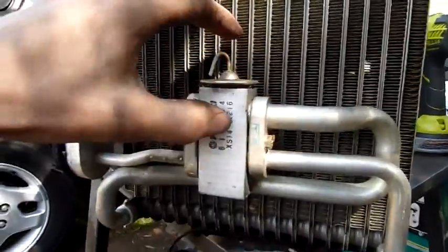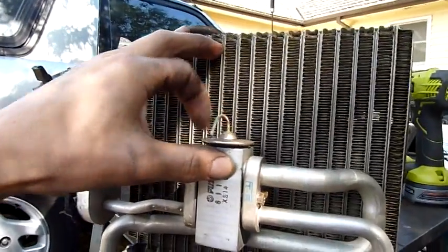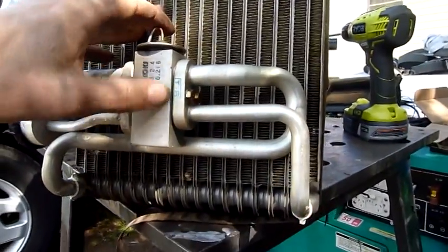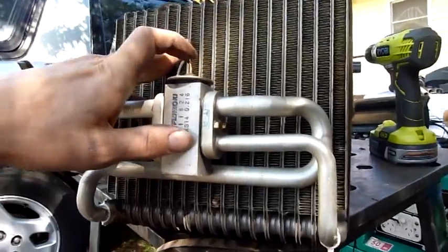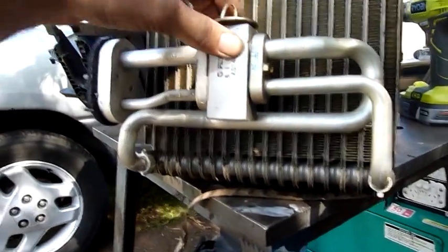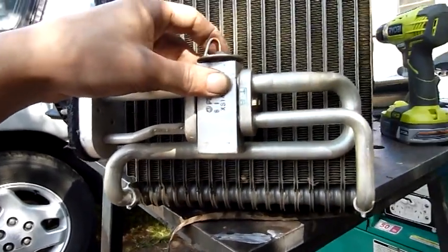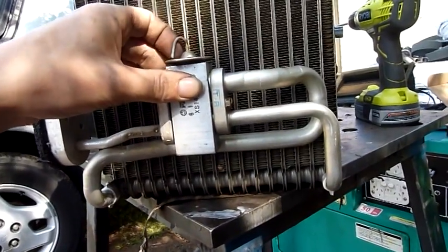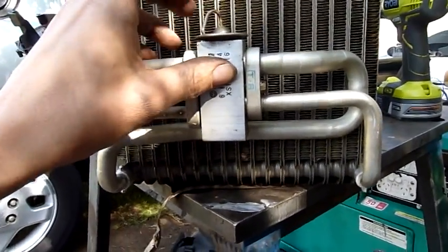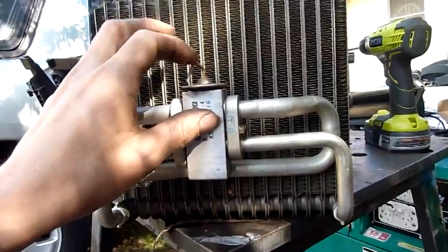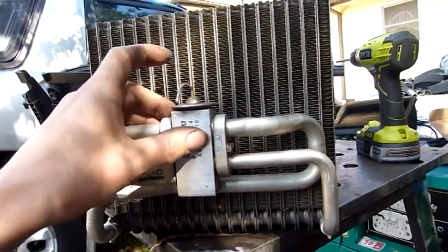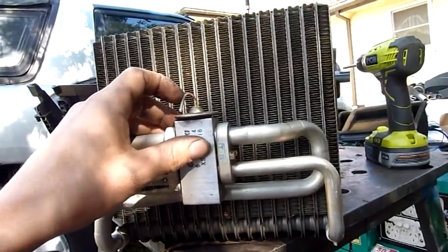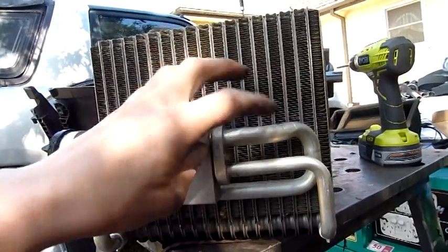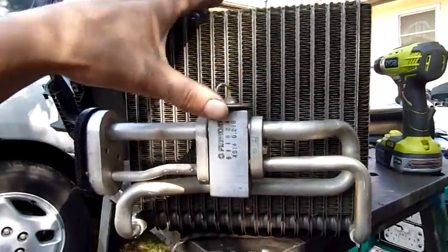But that's the thermal expansion valve, this little pickup there. It varies the flow of refrigerant through the coil depending on ambient temperature, or system temperature on the suction line. Or in this case probably air temperature is a little bit different. The heat pump or split system TX valves and conventional air conditioner TX valves have a bulb attached to the suction line.